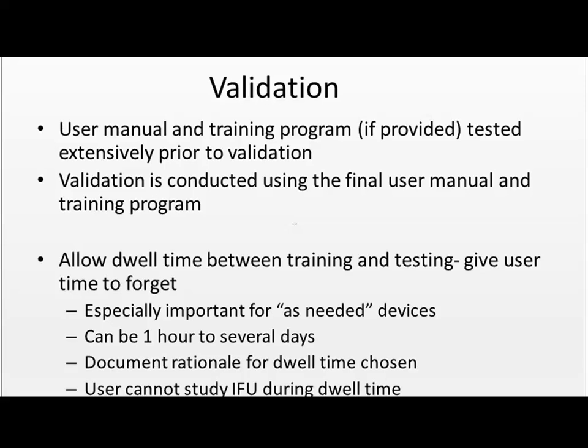Another very important point, the FDA concentrates on this. If you have a training program for users, you must allow a dwell time between training and testing. The purpose of this is to give the user time to forget what you taught him. It can be 1 hour, could be several days. You must document the rationale for the dwell time that you've chosen.